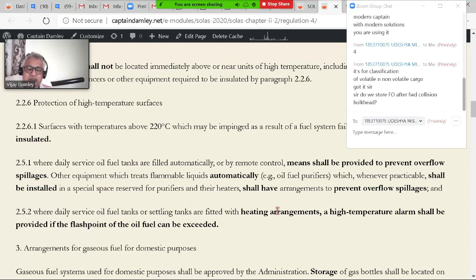And if you have got a heating arrangement, a high temperature alarm will be provided if the flash point of the fuel oil is exceeded. Here we are looking at settling tanks and service tanks. Now the settling tank, if you start heating it up, because the seawater temperature may be only 10 degrees, you have to heat up the oil before you pump it to the settling tank. And then you have to keep it hot, otherwise the whole purifier system may not work correctly. The liquid can freeze quite a lot, or it will become very viscous and you will not be able to use it. So wherever you have got heating, you must have a high temperature alarm as a logical rule.